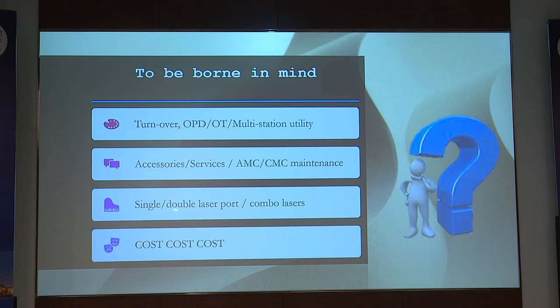And then the ports. Usually the console of the laser will have a single port or a double port, where you attach the slit lamp laser cable to the single port, or if you have a double port, you can attach the slit lamp cable to one port and the LIO to the other port. That saves you from changing ports again and again, and so increases the longevity of the cables, because once a cable gets damaged, you will be spending 1 to 2 lakh rupees on the cable itself. So before buying the machine, you need to look at whether the console has double ports or single ports. That's important.